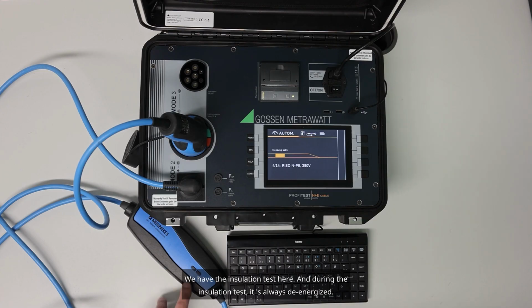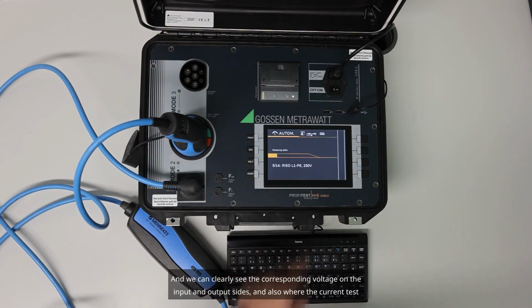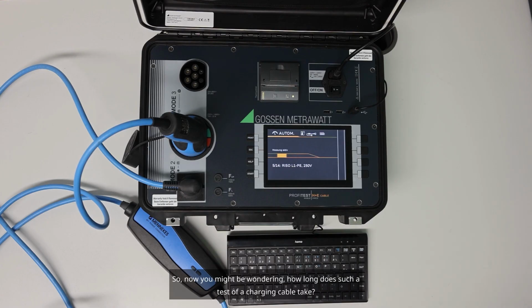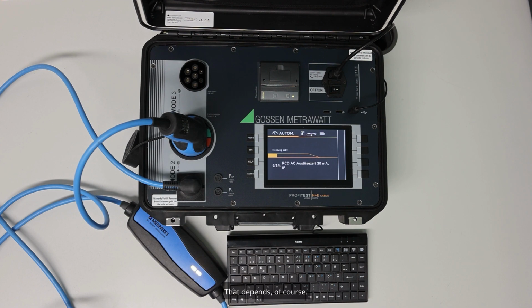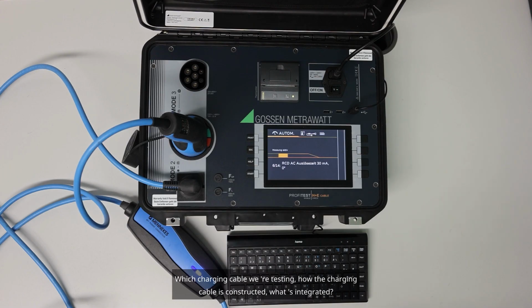In this case, we have the insulation test here. And during the insulation test, it's always de-energized. That means the charging cable is de-energized, otherwise you'd see it. And we can clearly see the corresponding voltage on the input and output sides, and also where the current test is taking place. So now you might be wondering, how long does such a test of a charging cable take? That depends, of course, which charging cable we're testing, how the charging cable is constructed, what's integrated. And depending on that, based on the manufacturer's specifications, we've defined the test cycle or the test sequence for you.